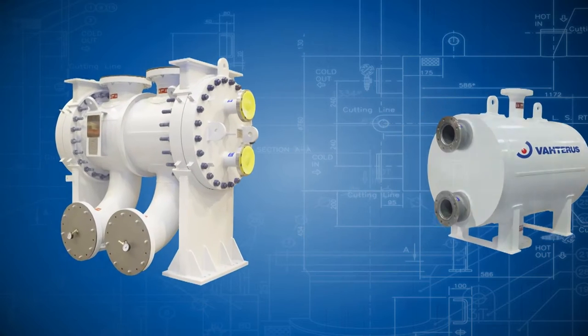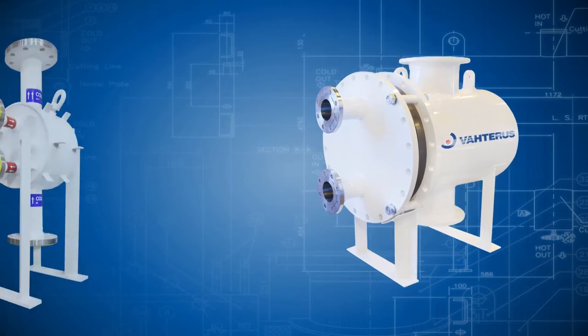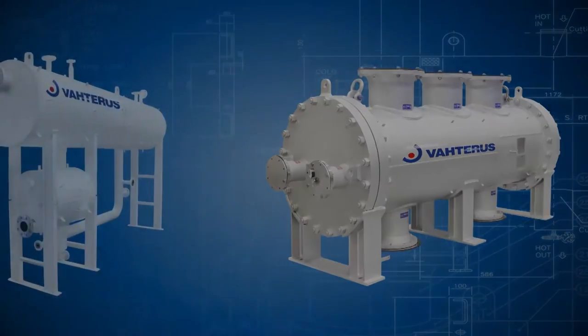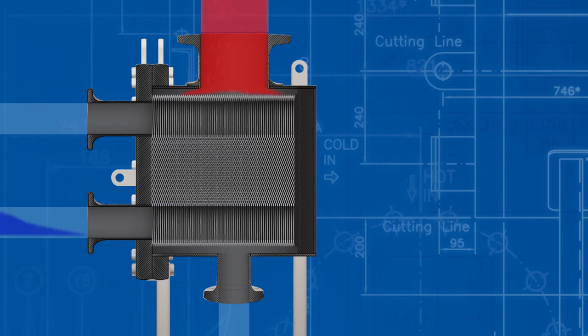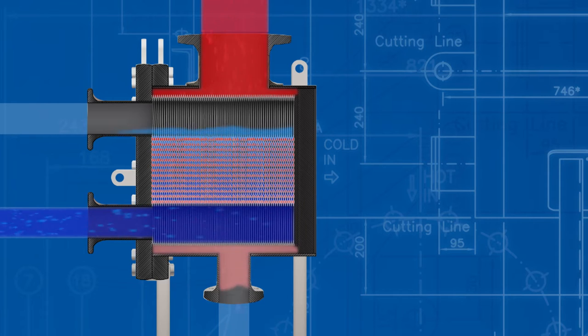Let us show you how to keep your process running with the Vahterus plate and shell heat exchanger cleaning video. As with all heat exchangers, any potential fouling issues should be discussed with the client at the design stage. Vahterus heat exchangers are individually designed for the client's application. A correctly designed plate and shell heat exchanger has highly turbulent flow. This turbulence creates a high wall shear stress which helps to keep the exchanger free from fouling.